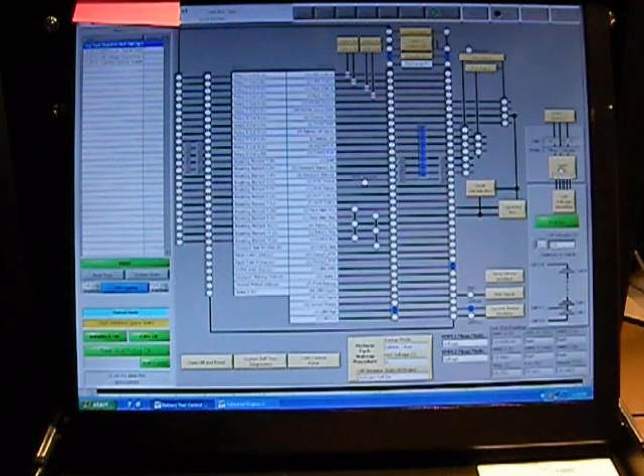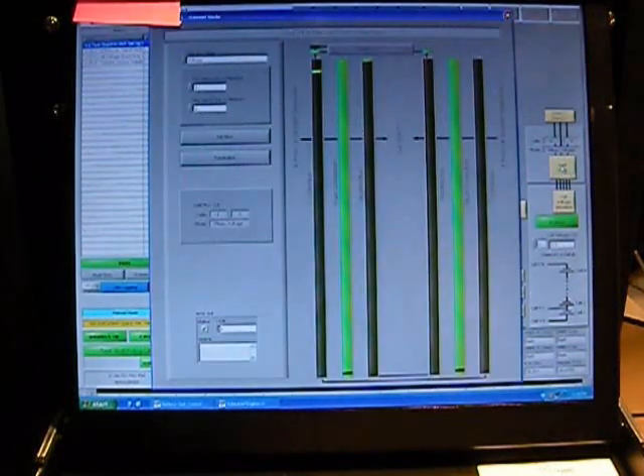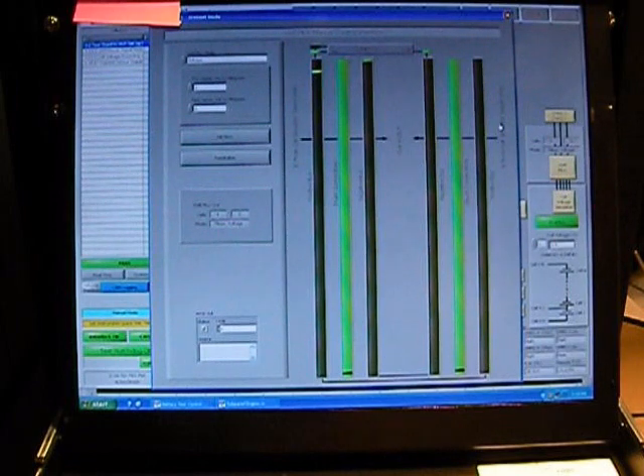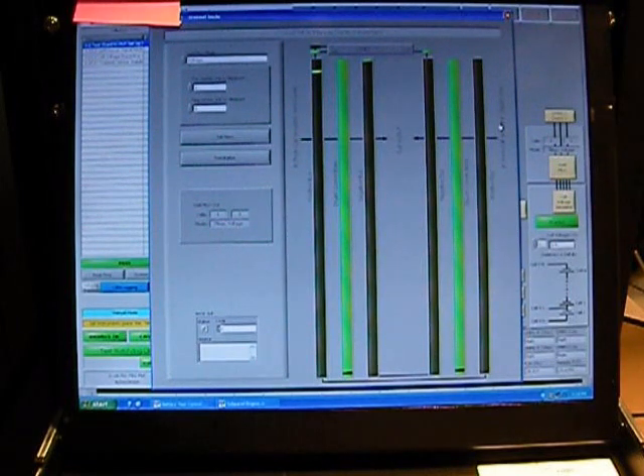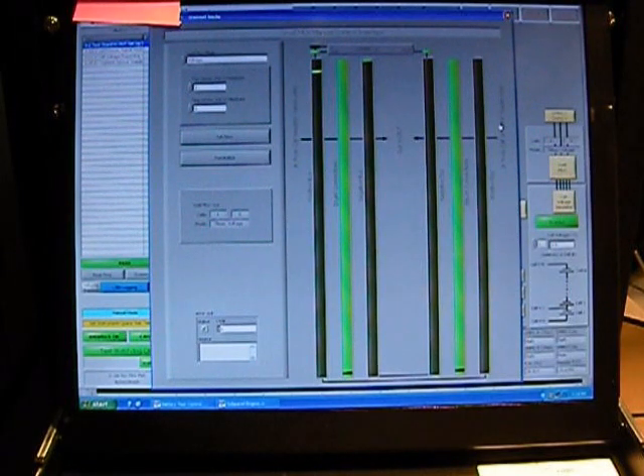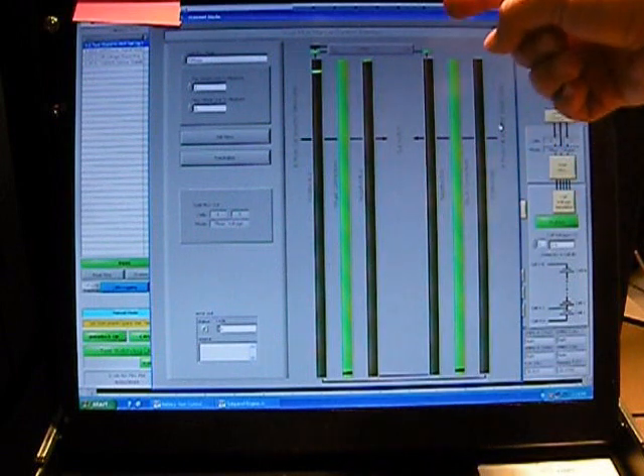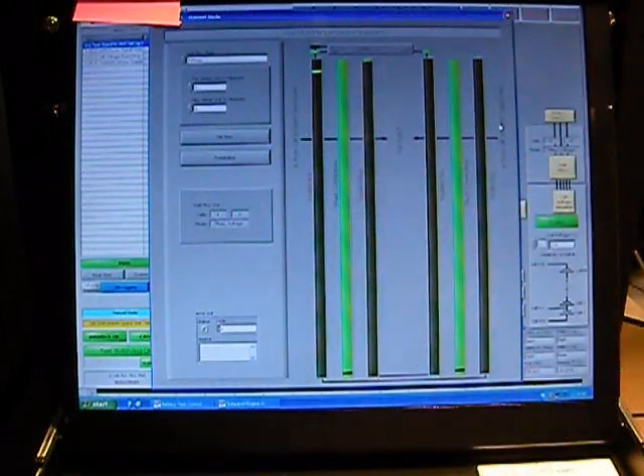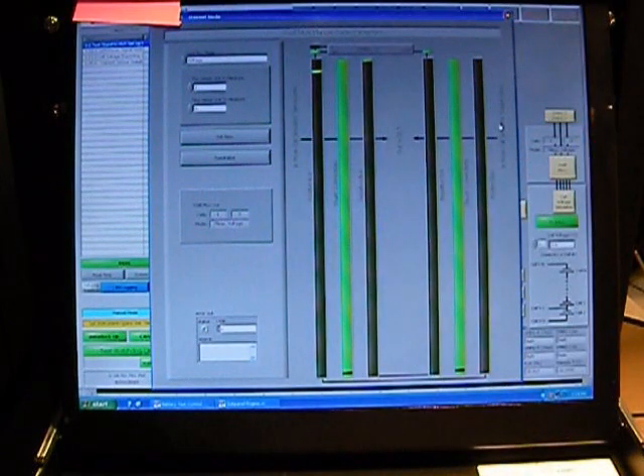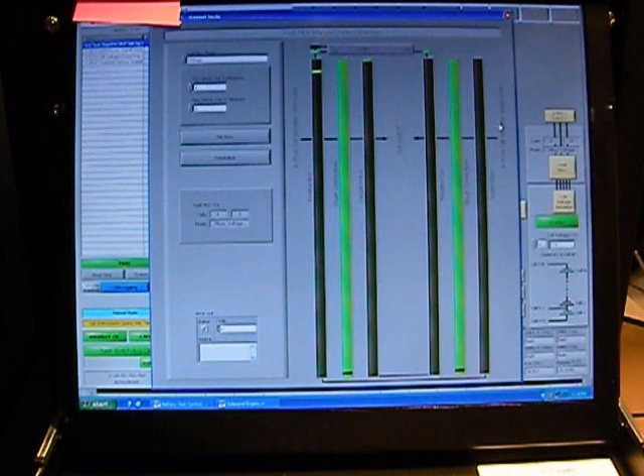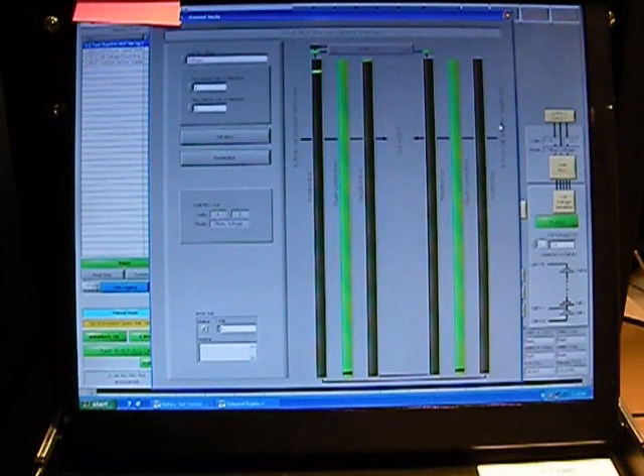The first thing we would do is click on the cell simulator mux, and this is just a subsystem that DMC has designed consisting of a bunch of different relays which can actually connect to any cell line coming out of the 100 cell stack simulator that we have in this BMS test system.